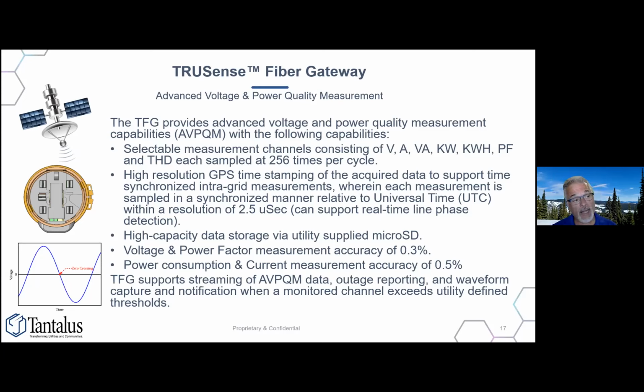When that happens, the trailing window of samples will be snapshot, and then we will continue to capture data again for another window that you define. And you can set what your coincident values are. So if voltage goes above a threshold for, let's say, 10 cycles, you can optionally capture amperage, you can optionally capture power factor, total harmonic distortion, and it'll capture all of that data, and it'll then notify you that an event has occurred. Because to stream this kind of sub-cycle data could overwhelm even a fiber network.